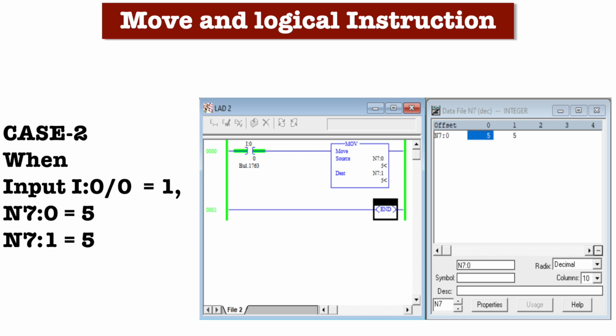In the same way, you can see in the diagram the data file is also represented, right? And you can see the value of N7:0 is 5. So when I provide the supply to the move instruction, it moves the source value to the destination. Initially the destination value is 0. So when I provide the supply to the move instruction by the switch, which is denoted by I:0/0, right? So when I press the switch, the value of the destination address changes to 5.